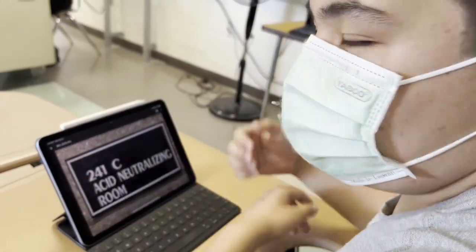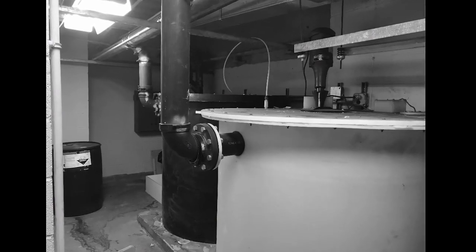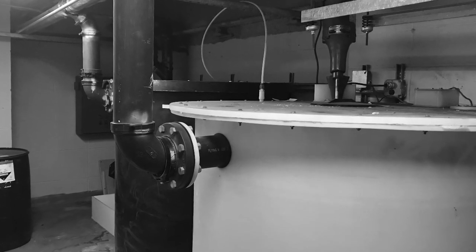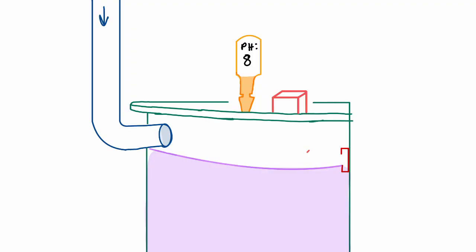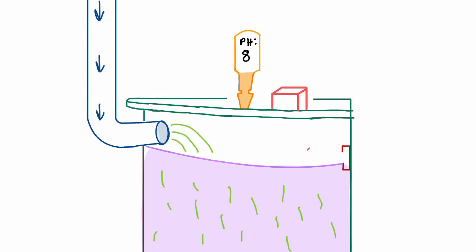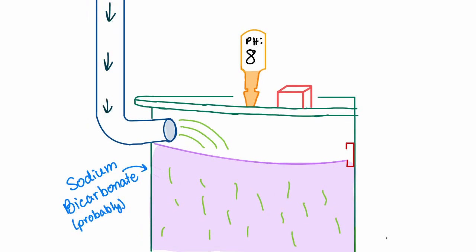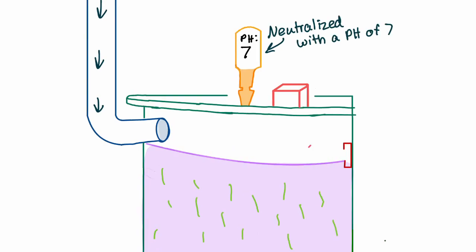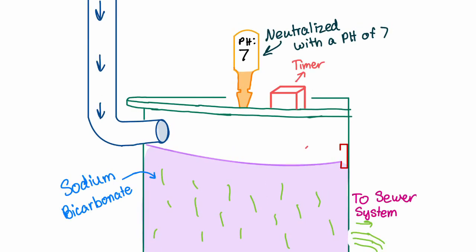We went to go talk to Mr. Katamani, a chemistry teacher at Townsend, about what was in the acid neutralizing room to demystify its workings. This is what he said: Pipes from the photography lab and the chem lab carrying acid lead to a giant vat with a neutralizer, possibly sodium bicarbonate. The neutralizer brings the pH up from acidic to neutral, tracked by a pH meter. If it's too acidic, nothing happens. But once the meter gets to 7, which is neutral, it's automatically dumped into the sewer system at a constant rate, tracked by a timer.